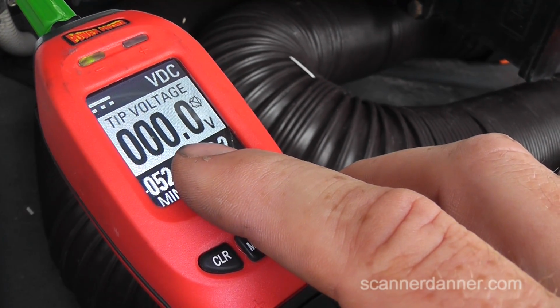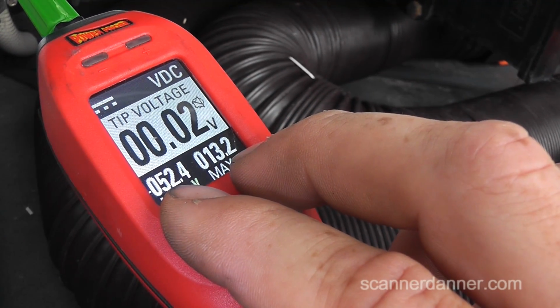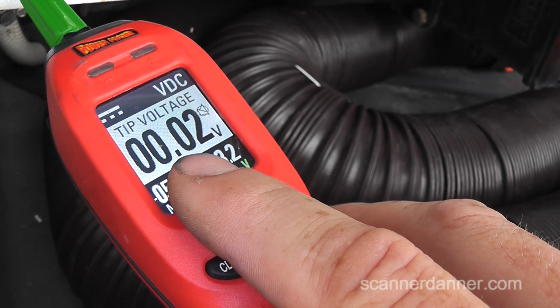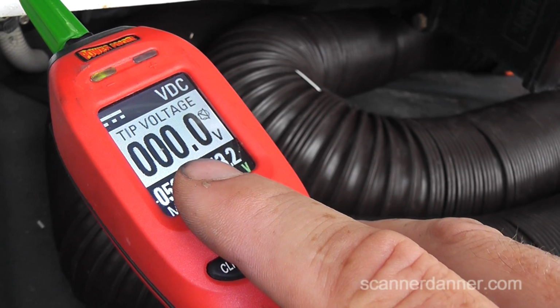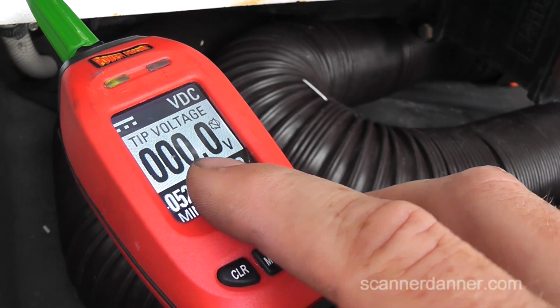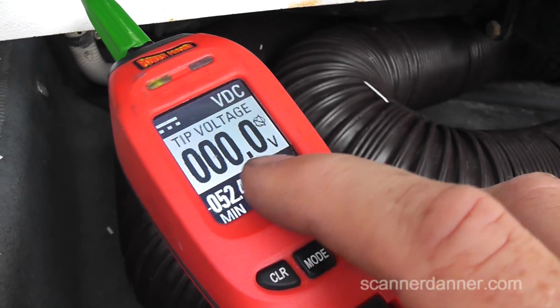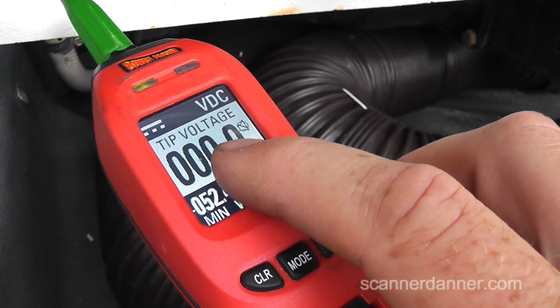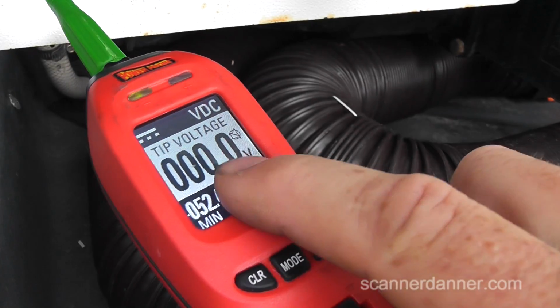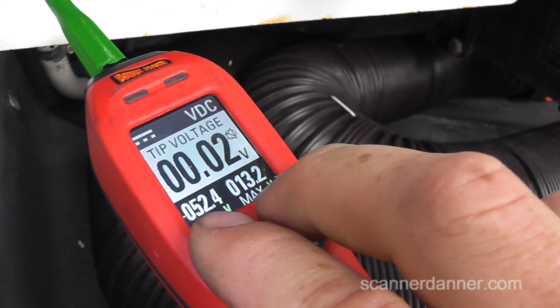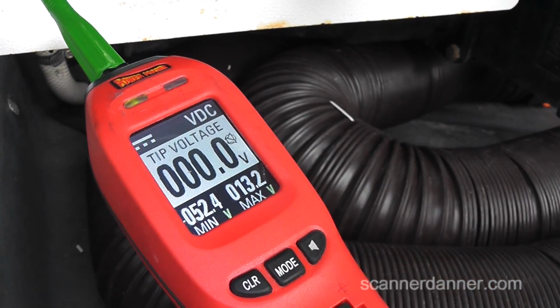It's going to be tough to maybe pick out with a regular multimeter. You can see I'm seeing it on the min-max scales here. But if you guys run into this in the future and you're troubleshooting these, with the valve on, with water flowing, we should have a steady 12 here, and we did not. It was surging and pulsing, and that voltage was even dropping up here. But remember, up here, this is an average of your voltage signal, so if you get really fast spikes, you may not see it up here. With a tool like this, we'll catch it on the min-max scales.